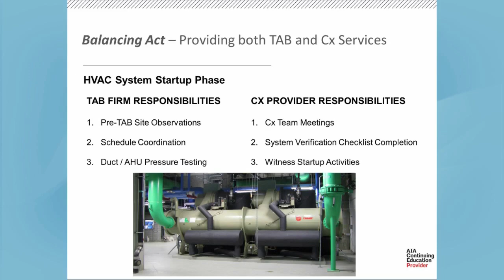Again, schedule coordination. You're going to see that I harp on this at every stage of the game, but it's usually what kills us on every project. And then again, at this stage, you may be past duct and air handling unit pressure testing, or you could have other similar requirements that the TAB firm needs to be present for, but they're not at a stage yet where they can actually start performing the primary test and balance testing. The commissioning provider at this point should be hosting regular meetings and trying to really coordinate the schedule. If we're doing startups, the commissioning provider should be just about complete with system verification checklists. At least in our firm, we try to make sure that those are completed even before the startups are allowed to occur, but sometimes that doesn't happen. And then witnessing the startup activities.